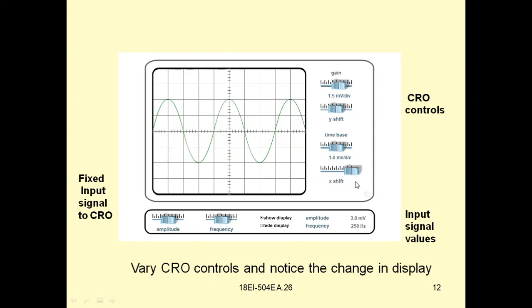Now move this. This is how you can move the signal. Horizontal shift. In any position you will get the same value. And by adjusting the time base, here the time base is 1 millisecond. Instead of that, I can increase it. Now how much is that? This one, 2 milliseconds, but here we do not know where exactly is the position, so use the horizontal shift to get it to the correct position.